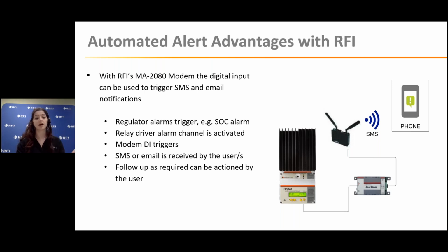They're all screw terminal Phoenix connectors, so really easy to connect up in the field or when you're testing it back at the office. So whatever that alarm is, whatever fault has been detected by the TriStar or the regulator on site, that's able to be triggered into the relay driver. Depending on how you've customized and programmed your relay driver, and exactly what aspects you've asked it to monitor or alarm on, it's able to take that signal and send it out through its alarm channels, through its digital output channels.